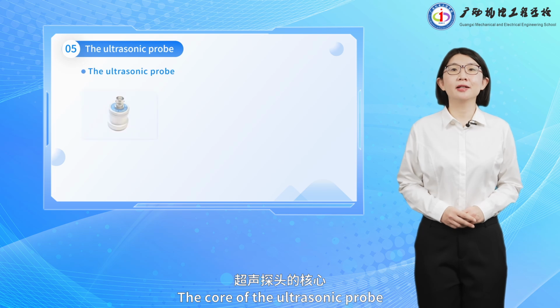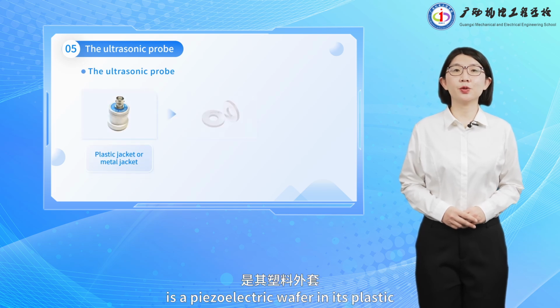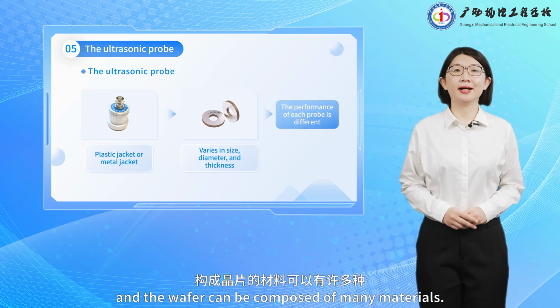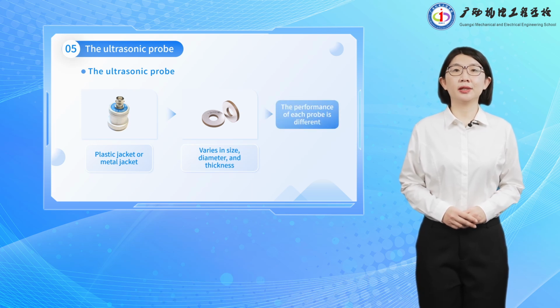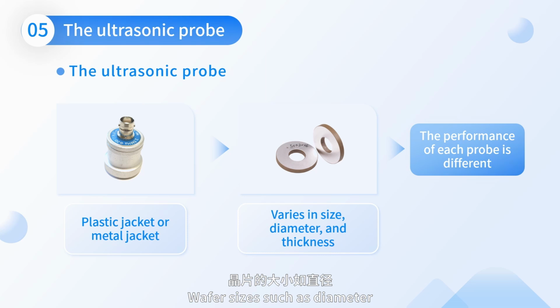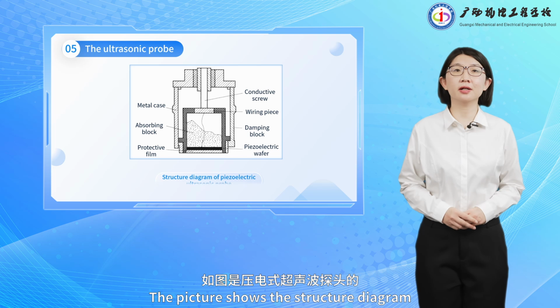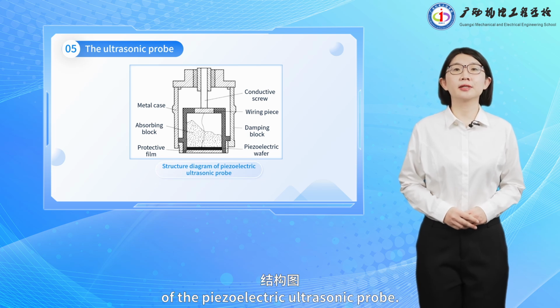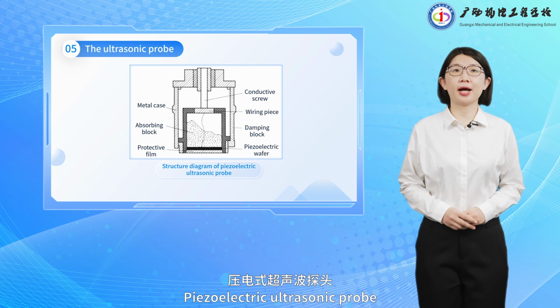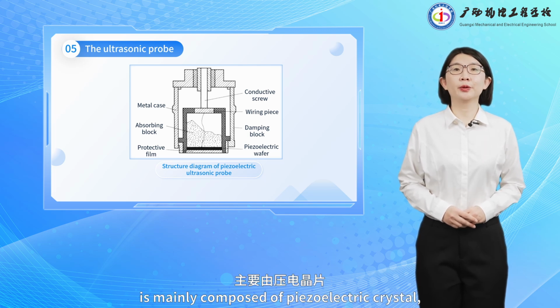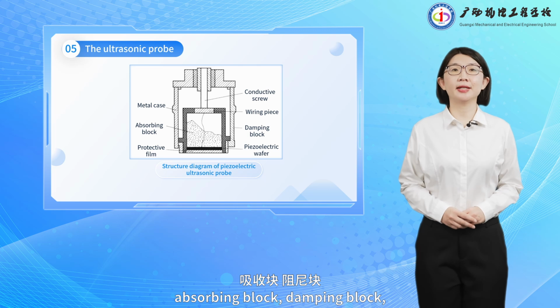The core of the ultrasonic probe is a piezoelectric wafer in its plastic or metal jacket, and the wafer can be composed of many materials. Wafer sizes such as diameter and thickness also vary. Therefore, the performance of each probe is different, and its performance must be known in advance before use. The picture shows the structure diagram of the piezoelectric ultrasonic probe. Piezoelectric ultrasonic probe is mainly composed of piezoelectric crystal, absorbing block, damping block, protective film, and so on.